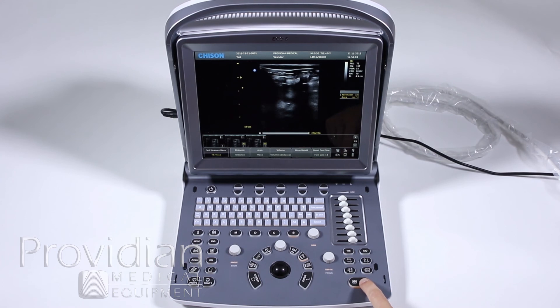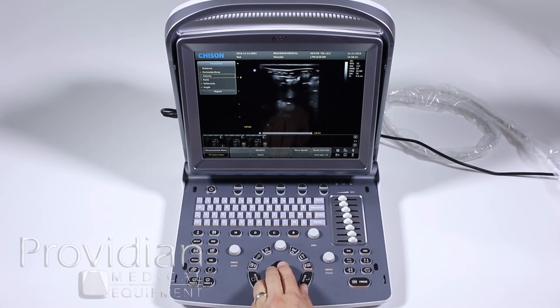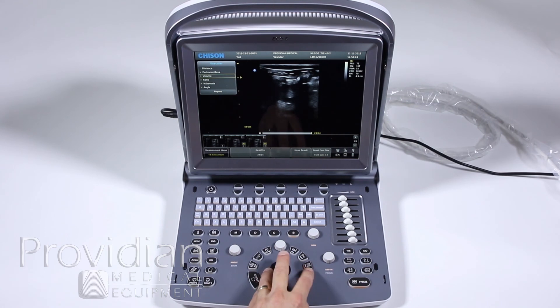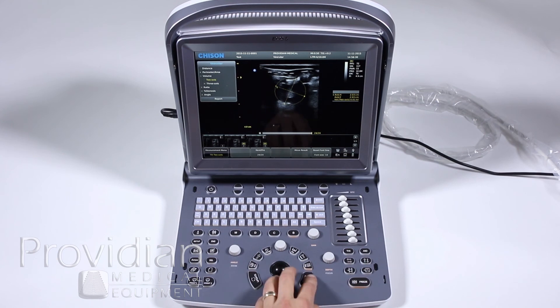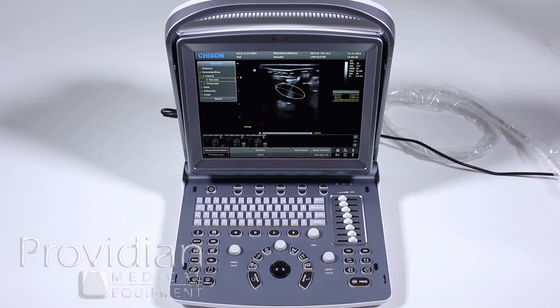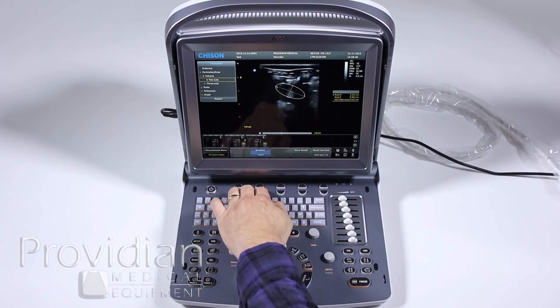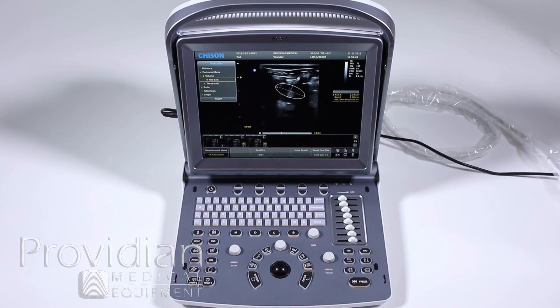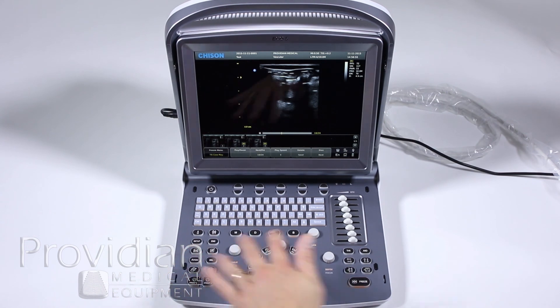For calculations, unfreeze the image and hit the calc button. Up here it shows vascular calculations because I chose the vascular preset — that can be changed. Using the trackball, select whichever item you want to measure, and that measurement will go to the report. Your measurement is saved right there. Note that if you want to take a measurement on a previous frame, you still have the CineLoop review and can scroll back to a different point to make a measurement there as well. To remove those, hit the delete key, and hit exit to get rid of the menu.